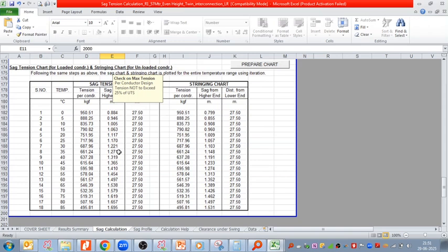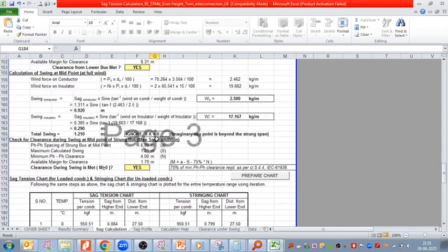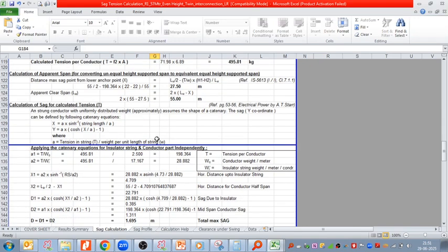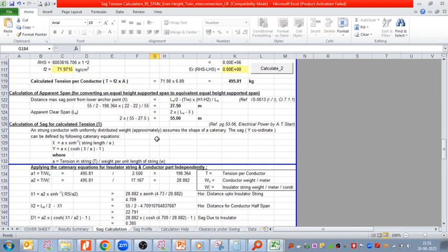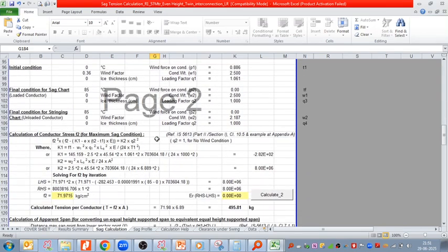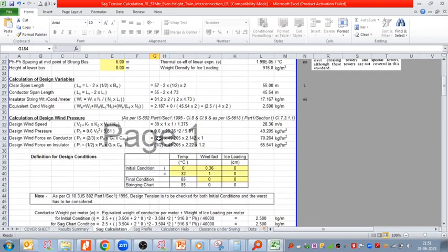So in short circuit force calculations, how do you perform it in your company? First you perform SCF, so which tension do you consider? Sir, final tension. Here we have two cases. For the initial case, if my conductor is twin, we can obtain 2000, as you said earlier. And for the 75 degree, whatever value comes in the second tension value, we can consider that tension value for the 75 degree temperature, 1 second.